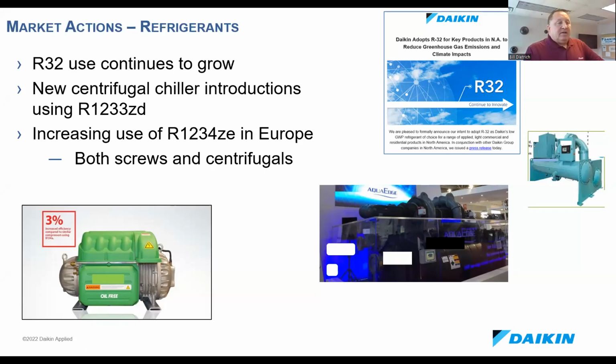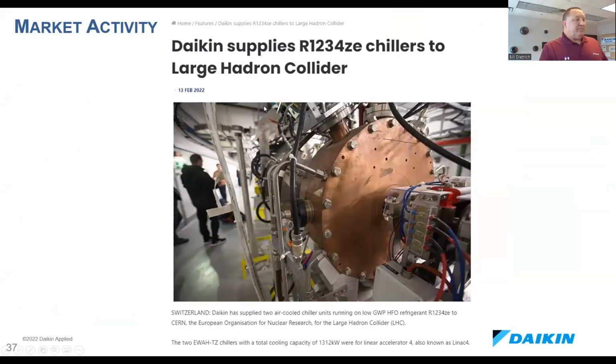Again, like I said earlier, on the A2L refrigerants, one of the easier places to apply them will be in air-cooled chillers that are sitting outside. This was another 1234ZE chiller example. Again, very low GWPs, so there's a lot of interest, but you just have to make sure you can deal with the slight flammability in a safe way.